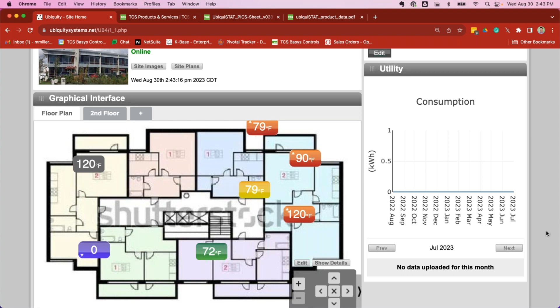If we put a thermostat on top of a rooftop unit, we're going to get the discharge air, the space temperature, and see when the fan starts and stops. We BACnet into that rooftop unit and get everything - the pressures the refrigeration circuit is running, the automated alarms the unit initiates from a BACnet perspective, and all the different stages of the condenser fans if available.